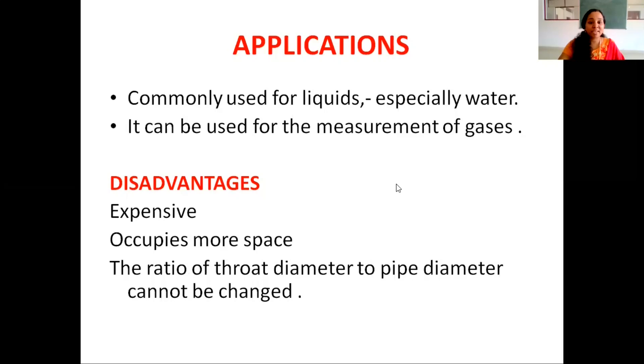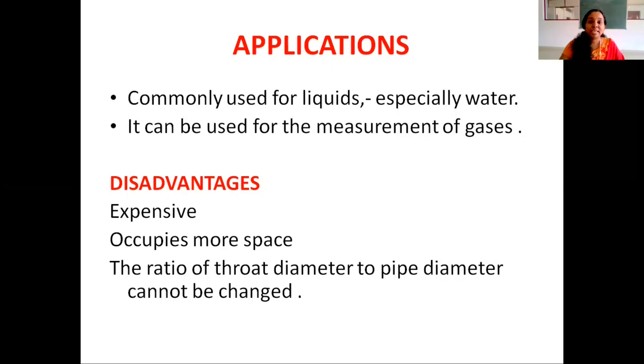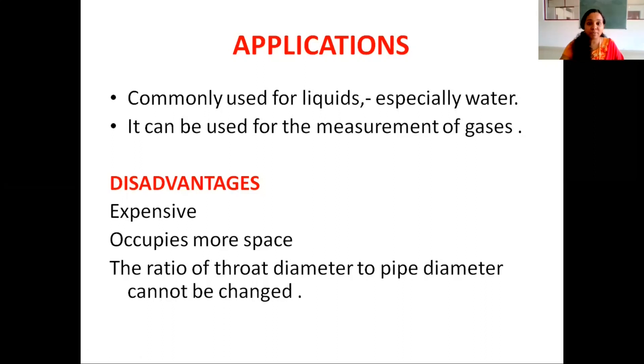The important applications of Venturi meter: it is mainly used to measure the flow rate of liquids, especially water. It can also be used for the measurement of gases. Regarding disadvantages: Venturi meter is more expensive, it requires more space for occupancy, and the ratio of throat diameter to pipe diameter cannot be changed.